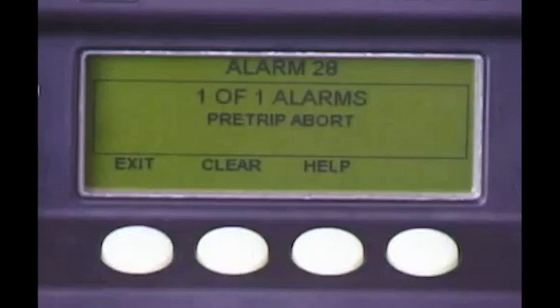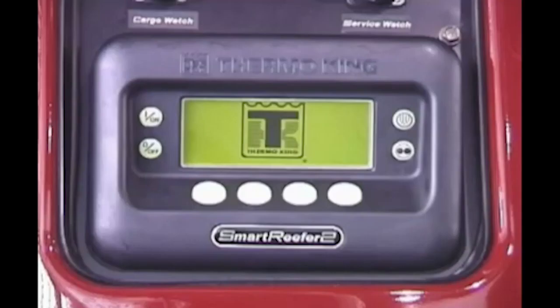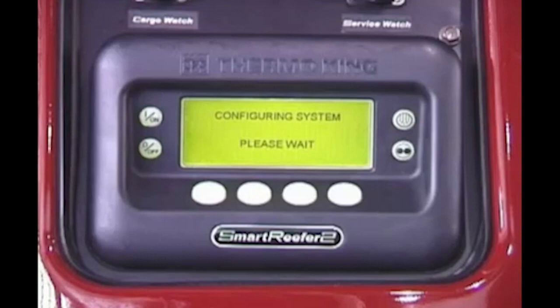If an alarm occurs while you're on the road, the alarm screen will appear and the display will flash. The alarm number, quantity of alarms in memory, and a description of the alarm will be displayed. To clear the alarm or alarms, press the Clear key. If the alarm successfully cleared, no alarms will be displayed. If they did not successfully clear, or the symptoms that caused the alarm still exist, the alarms will likely re-occur. If they do, contact your ThermoKing dealer immediately for assistance. After the alarms are cleared, no alarms should appear, indicating there are no alarms in memory. The unit should then automatically pre-heat and start.